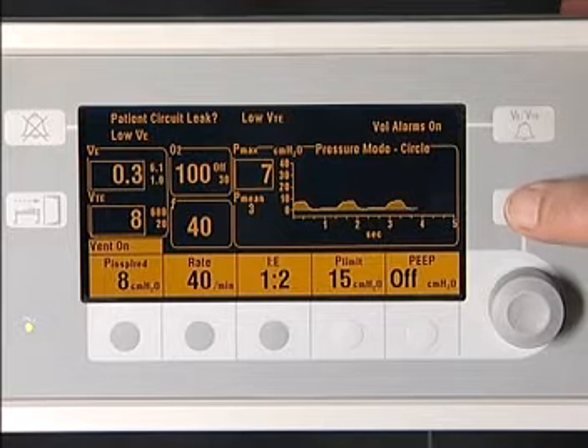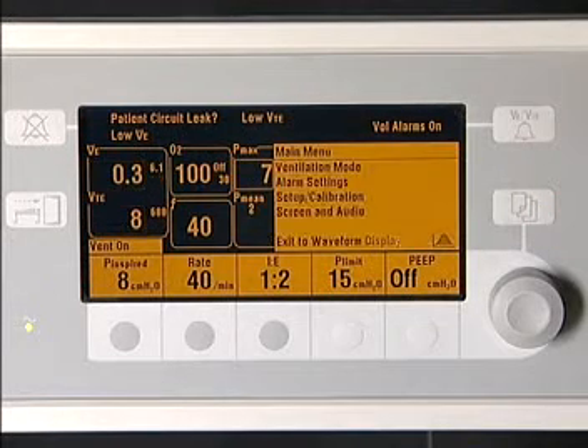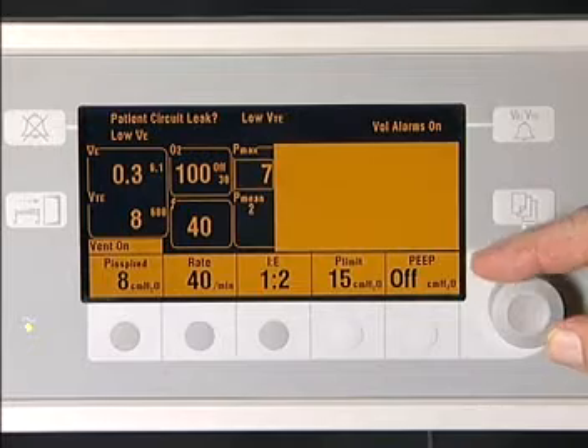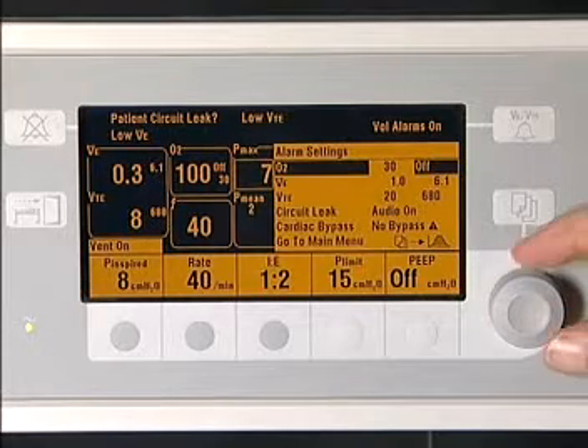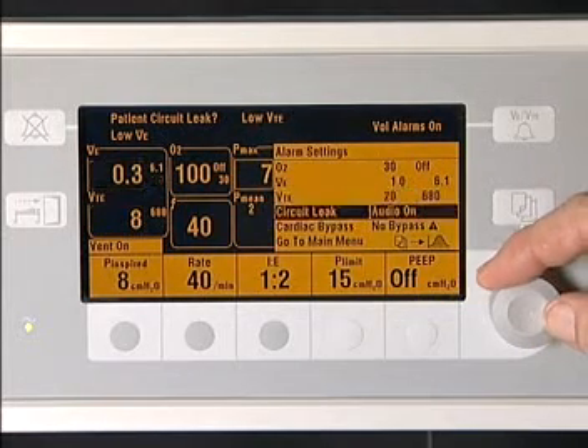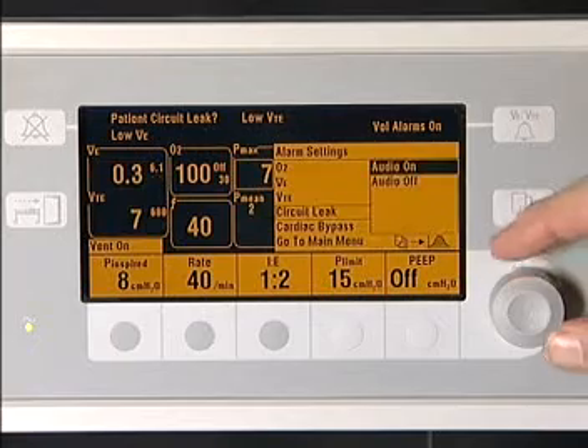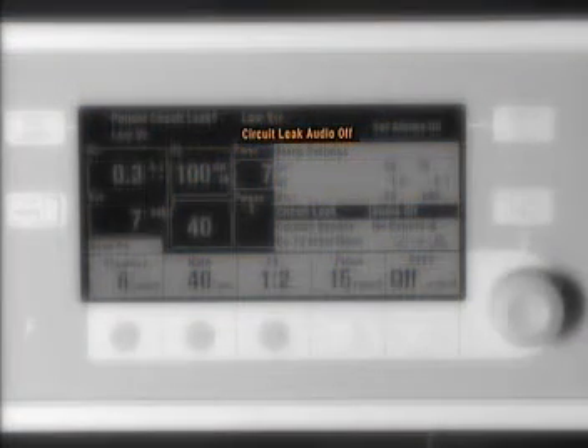If the operator has a known acceptable leak, such as with an uncuffed tracheal tube, selecting Circuit Leak Audio Off in the Alarm Settings menu will quiet the alarm. The message will remain until end case is processed or the choice is deselected.